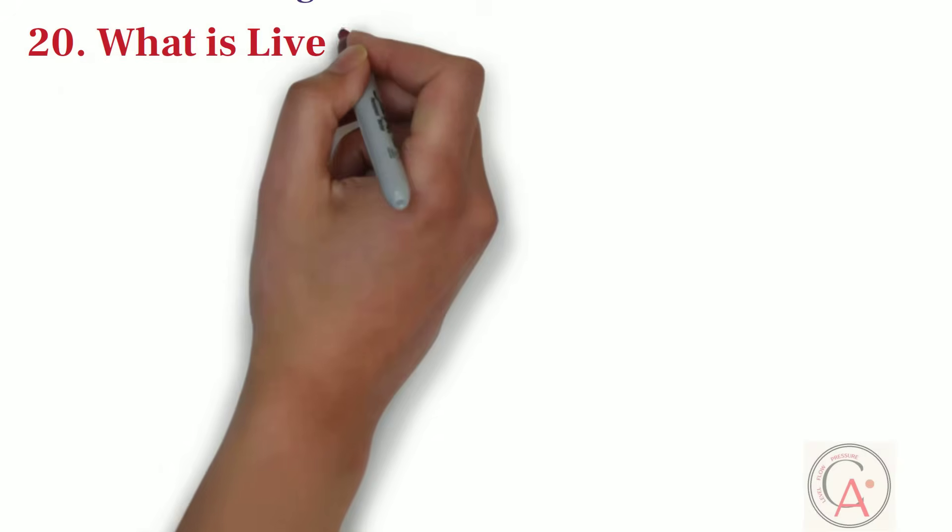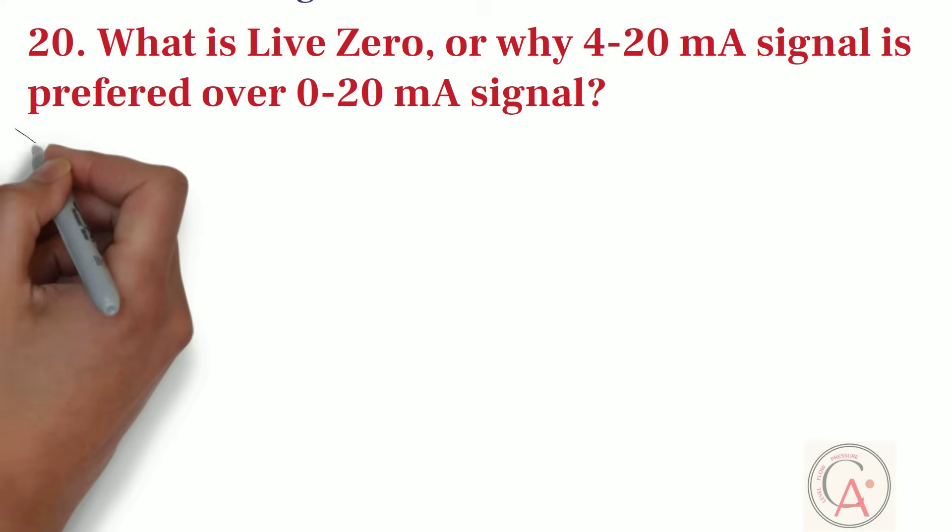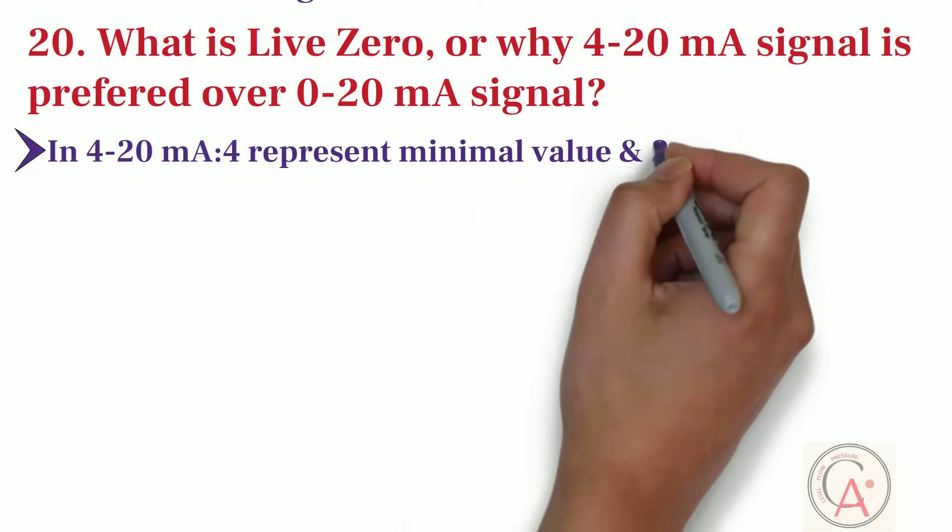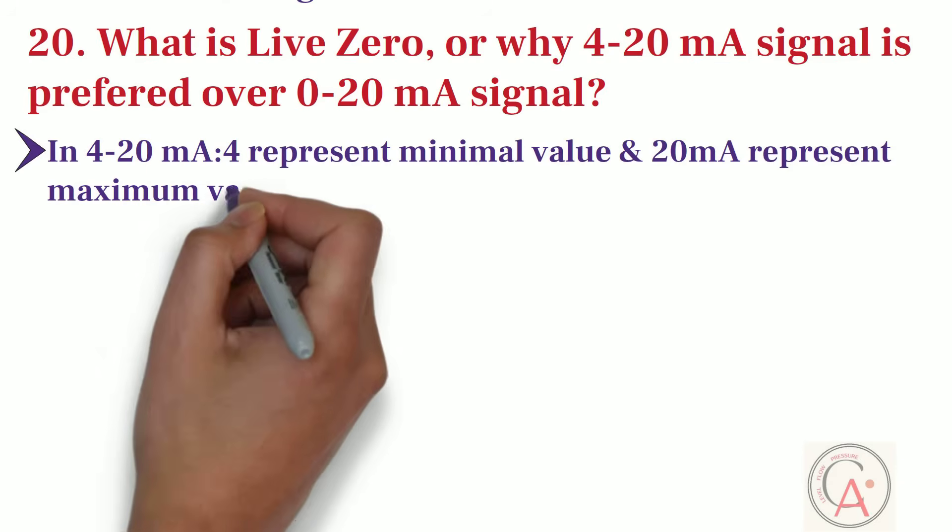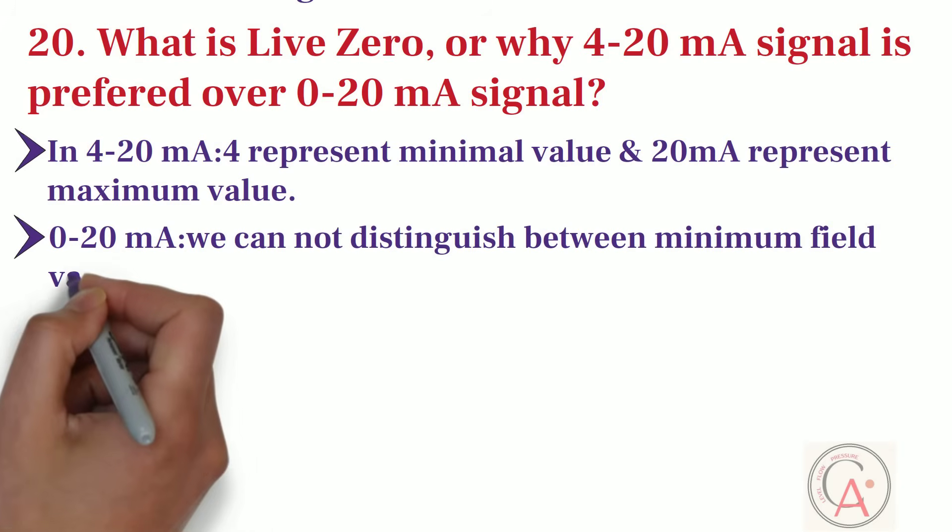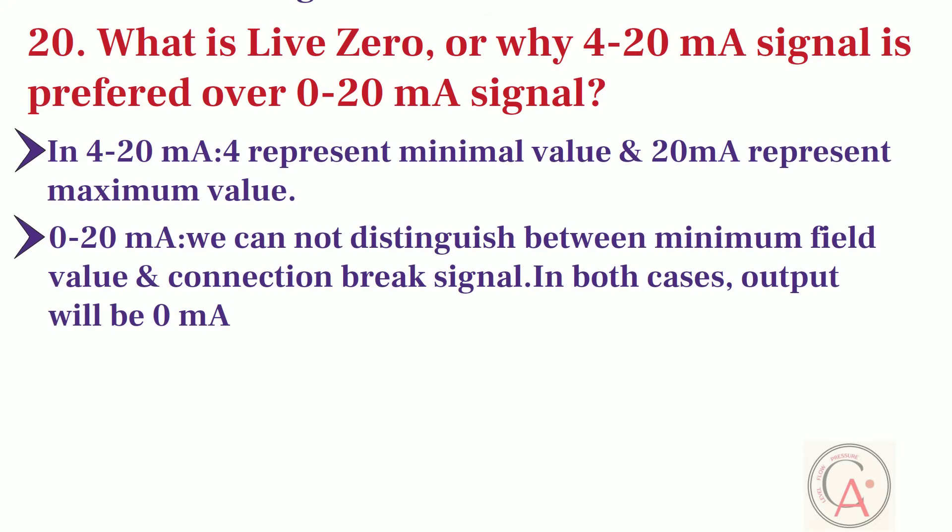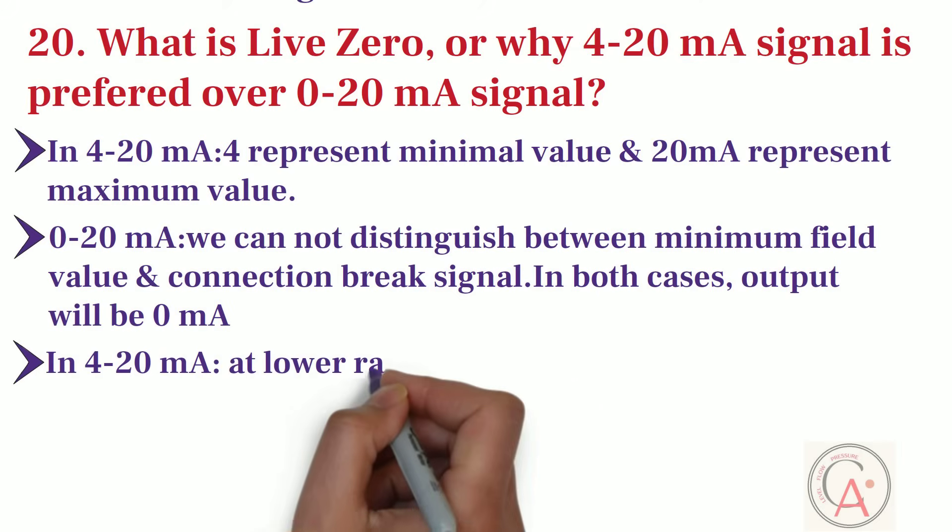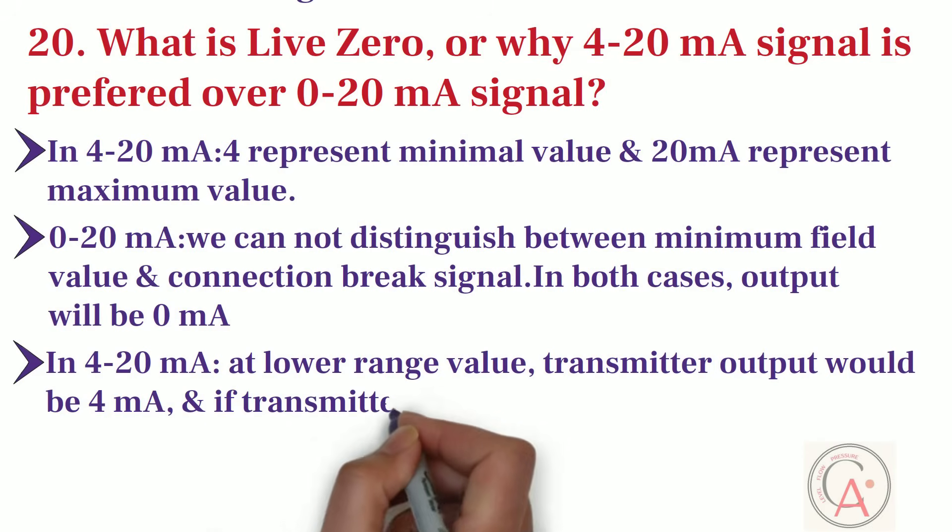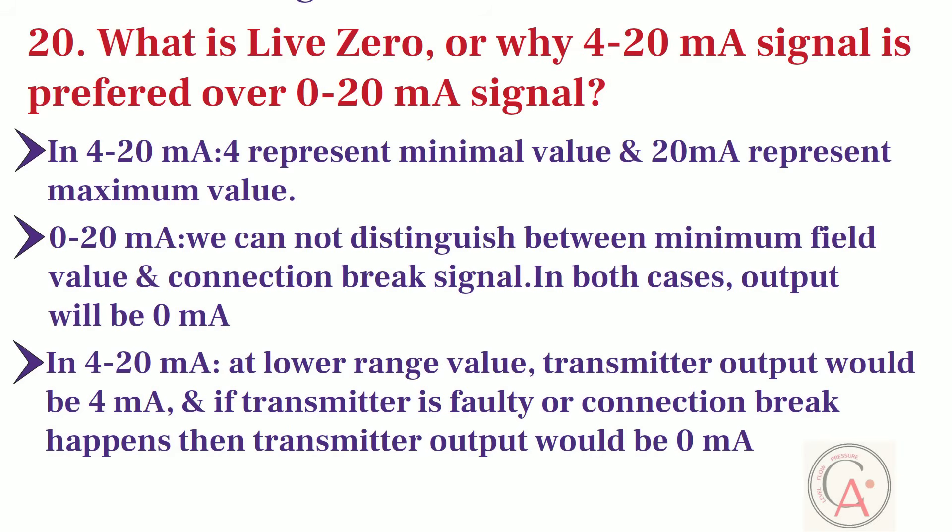Another important question is, what is live zero, or why 4 to 20 mA signal is preferred over 0 to 20 mA signal? In 4 to 20 mA signal, 4 mA represent minimal value, and 20 mA represent maximum value. With 0 to 20 mA signal, we cannot distinguish between minimum field value and connection break signal. In both cases, output will be 0 mA. However, in 4 to 20 mA signal, at lower range value, transmitter output would be 4 mA, and if transmitter is faulty or connection break happens, then transmitter output would be 0 mA.